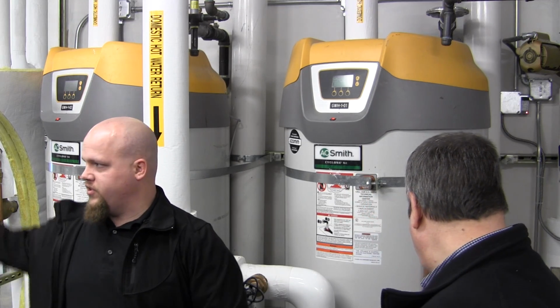You also, on the condensate side, have your condensate neutralizers that you'll want to check probably a couple times a year, and you'll get a good feeling of how often those need to be replaced or refilled. Those are the refillable type. Sorry for not knowing this, but what is that? It's basically a plastic tube that has on the back side a clean out with a square nut. So you can take that out, and then it has limestone chips in there that neutralize the acid because your condensate's acidic, and we can't dump that to drain. Okay. So basically, over time, those limestones will dissolve away, and then you need to replace them with more. It just comes in a little packet? Yeah. Usually, you can buy a 25-pound bag of limestone chips, and you keep it tucked away in a corner for these, and then your boilers also have them.